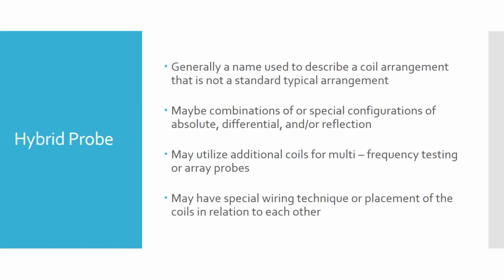You can add things like a couple different size pickup coils or driver coils, so you can run them at different frequencies. Multi-frequency testers can send a high frequency, low frequency, back and forth, switching several times a second.